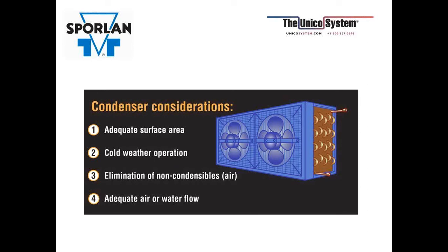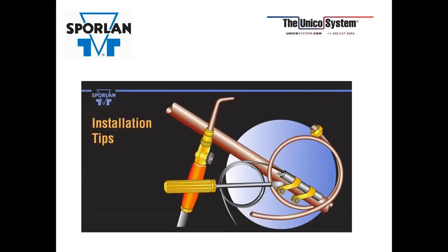The TXV can handle fluctuating head pressures, but if you go too extreme, then you're going to run into some hunting issues. And number 3, elimination of non-condensables, air. Non-condensables can add water and oxygen to your system, causing the formation of sludges, acids, rust, and copper plating, among other things. The only way to prevent their presence is to properly evacuate the system when it's first installed, and also to evacuate it during any subsequent service calls where you break into the system. If you break into the system, you need to make sure you evacuate again. And then number 4 is, once again, making sure you have essential to maintain reasonable head pressure for good system performance.